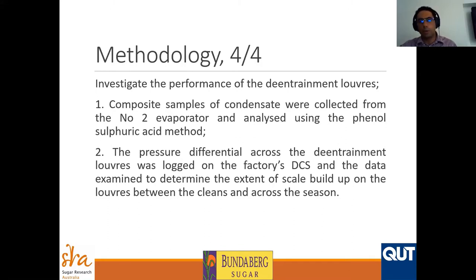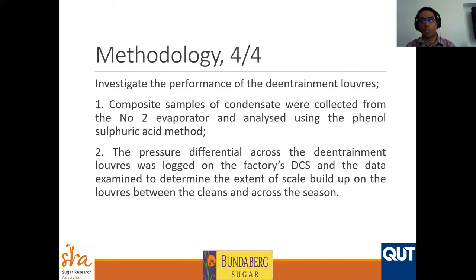The fourth part of the project investigated the performance of the louver entrainment system. We measured the pressure drop across the louvers to assess scale formation and the effectiveness of chemical cleanings. We also measured how much juice carryover occurred in the vapor coming out of the entrainment louvers.